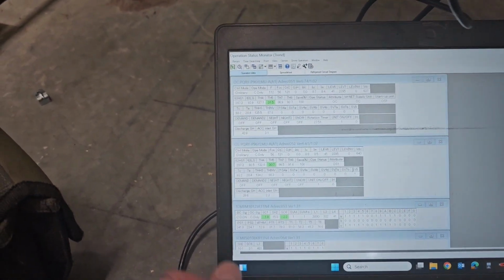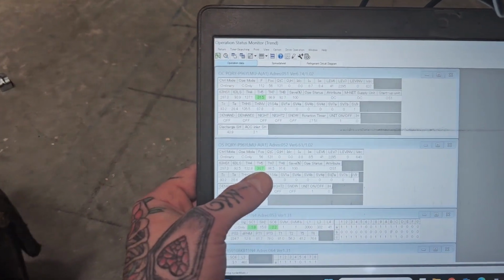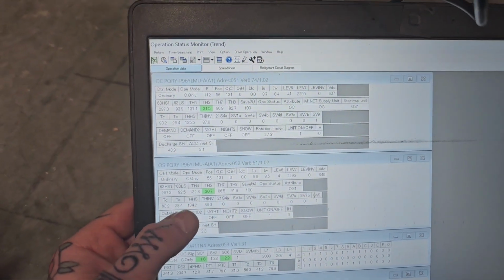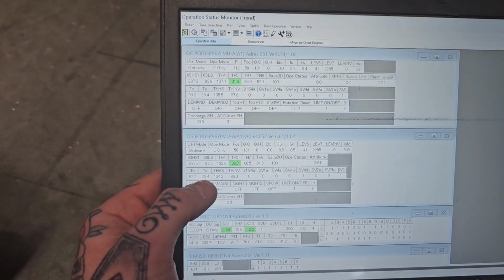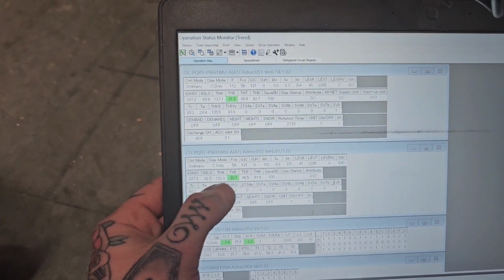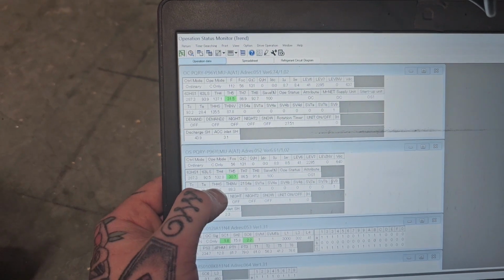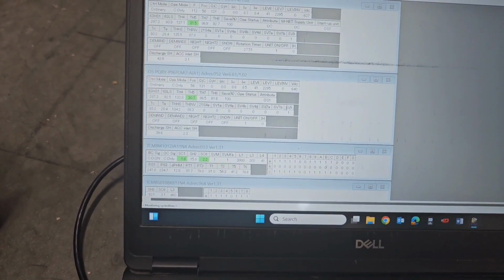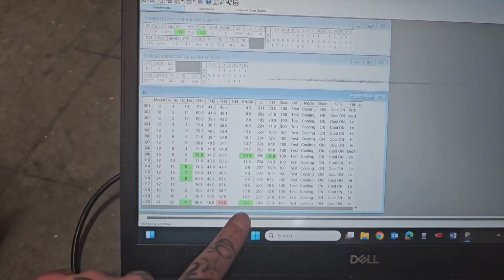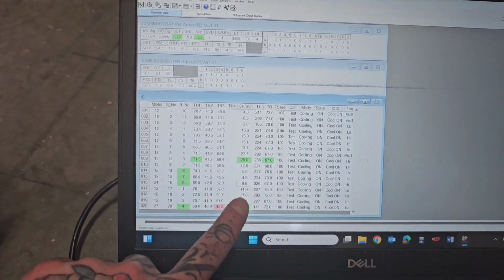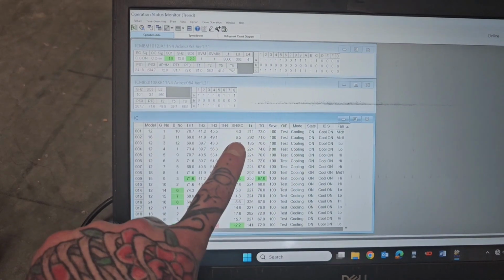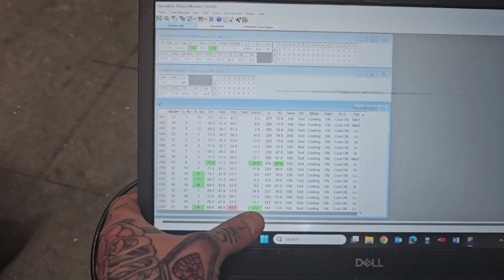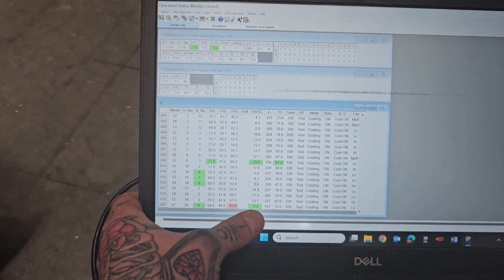Yet when you come out to your outdoor units, you've got a TH5, which is your suction line entering your accumulator, of 30 degrees. Your suction saturation temperature is 28. So you've got 2 degrees of superheat at your outdoor unit. Yet you've got 15 degrees of superheat at your branch controller, and your indoor units all have relatively high superheat. Some are lower. You know, we got a 4, 4, 6, 2.9. But that definitely stands out.